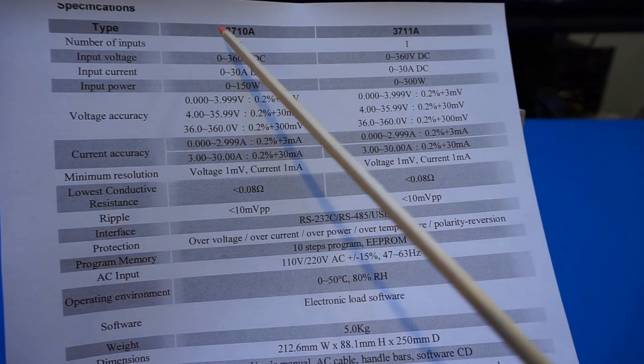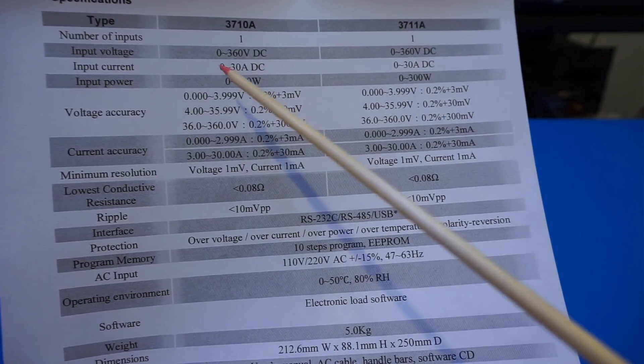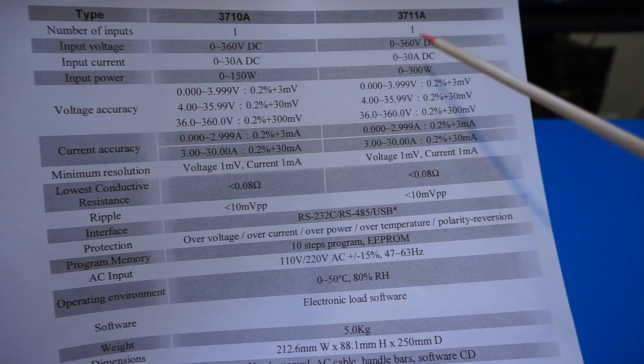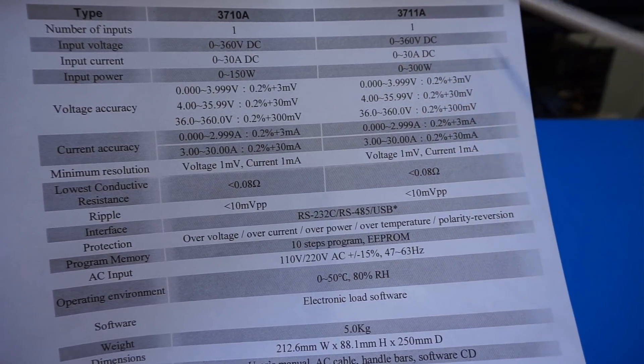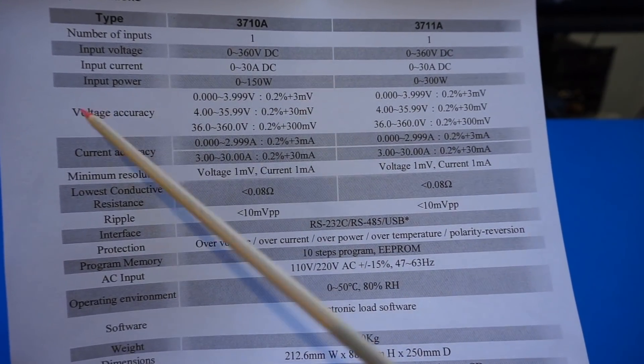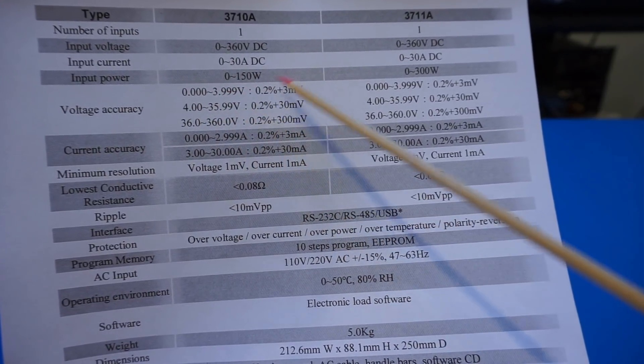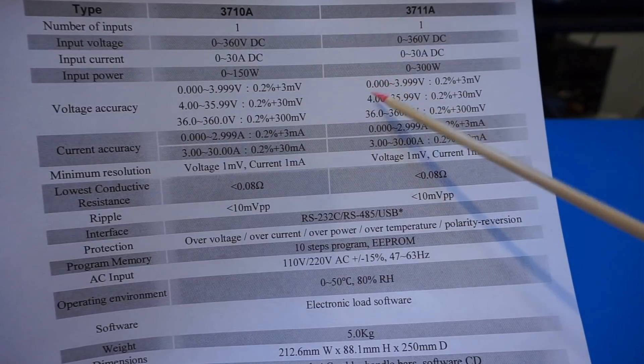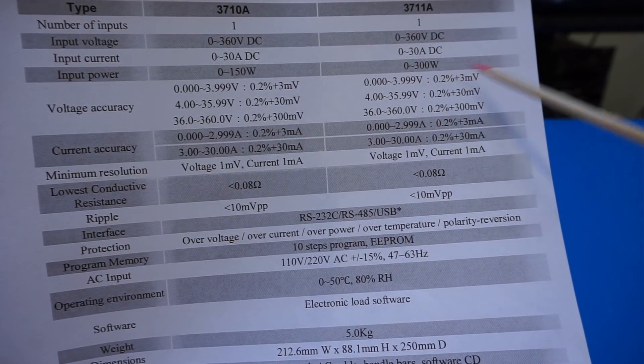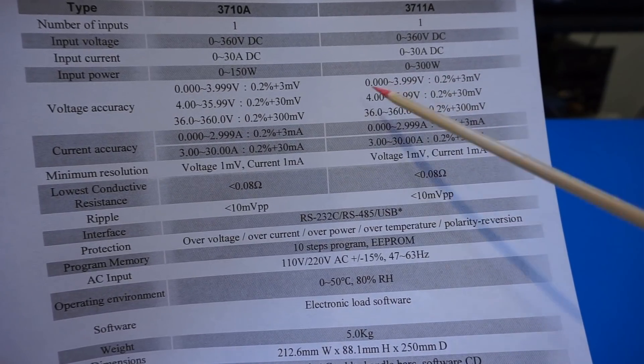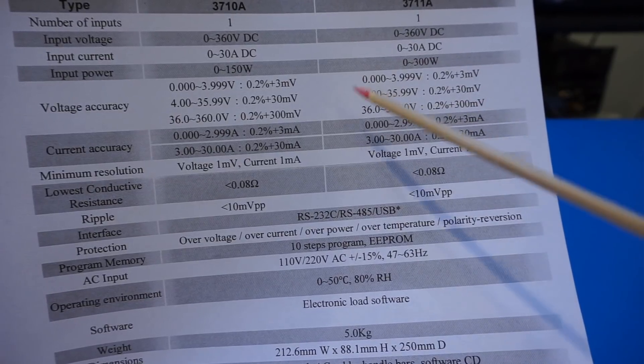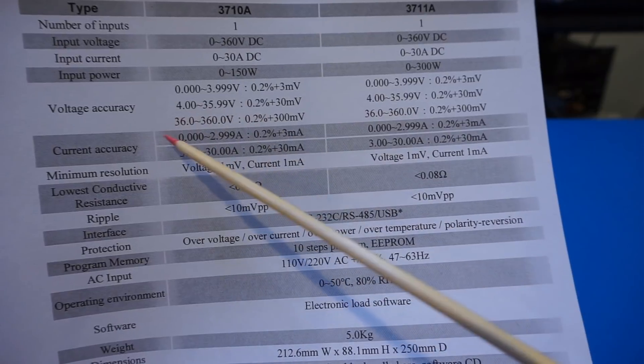So let's first take a look at the specifications here and I have the printouts here basically having the 3710A and 3711A side by side and as you can see the only difference seems to be the input power. For the 3710A it's 0 to 150 watts whereas the 3711A the maximum dissipation is 300 watts. Everything else looks pretty much identical. Now if you look at the voltage accuracy here from 0 to 3.999 volts the accuracy is 0.2 percent plus 3 millivolts. So this suggests that the unit is using at least a 10-bit DAC because we have 1,024 steps that gives you roughly 3 millivolts here and you can see that the next range is 30 millivolts because the range is 10 times larger and 300 millivolts for the even higher voltage range. The same goes for the current accuracy as well.